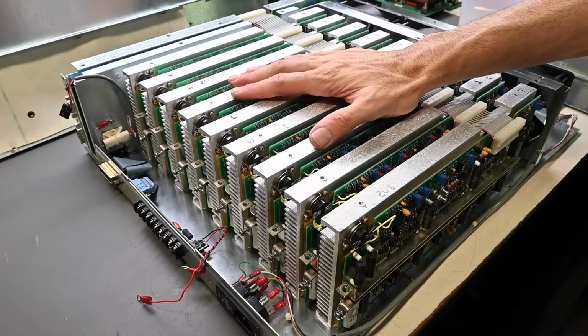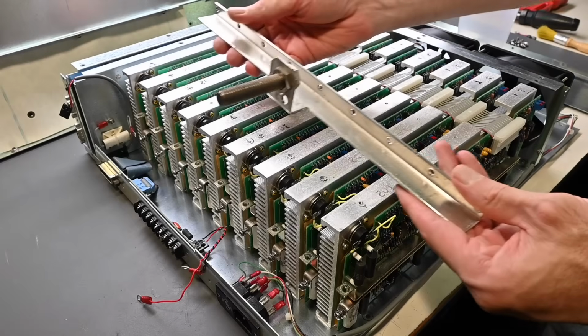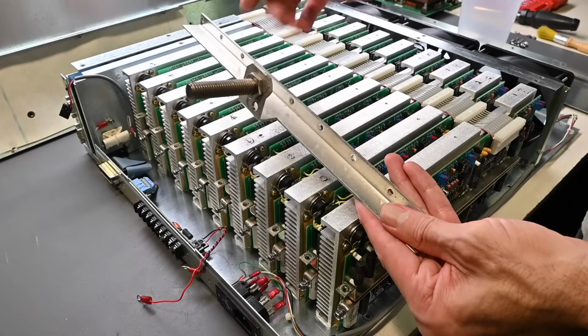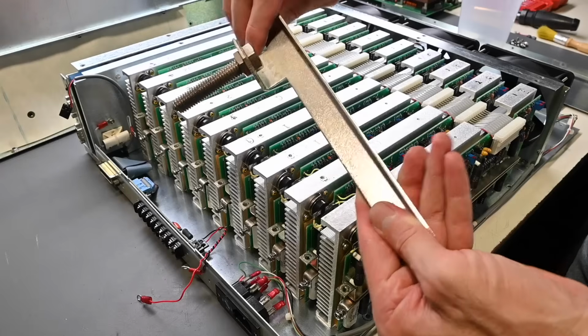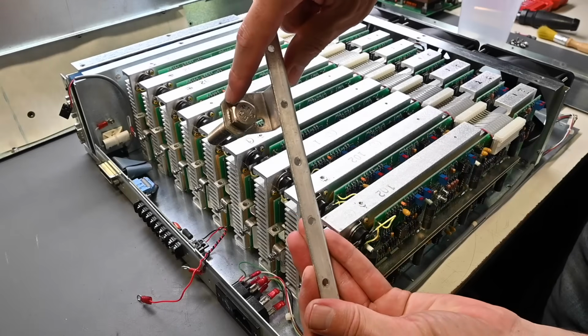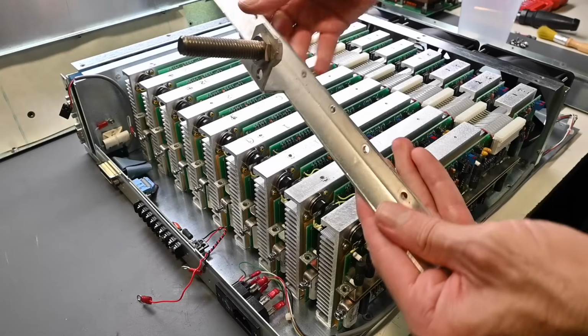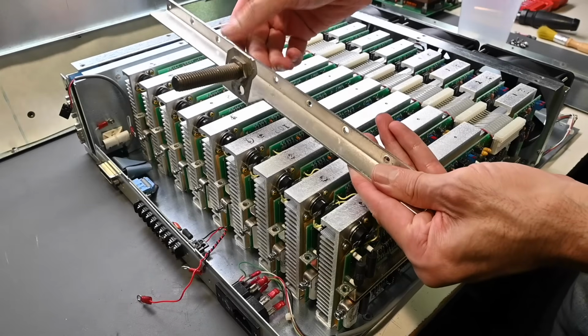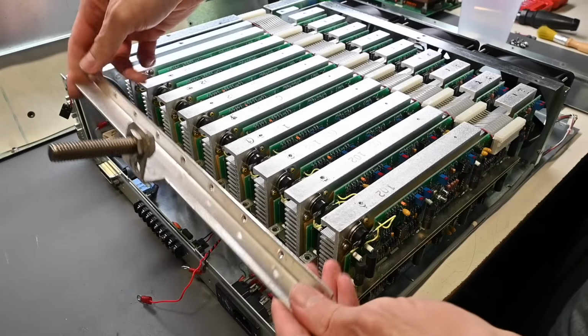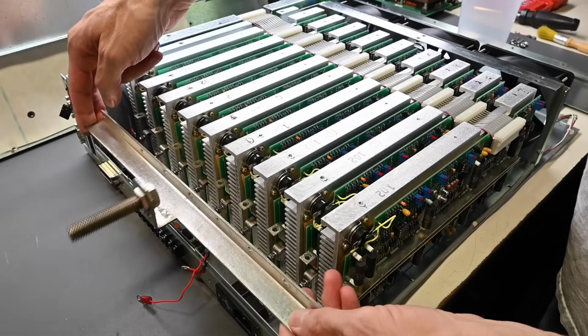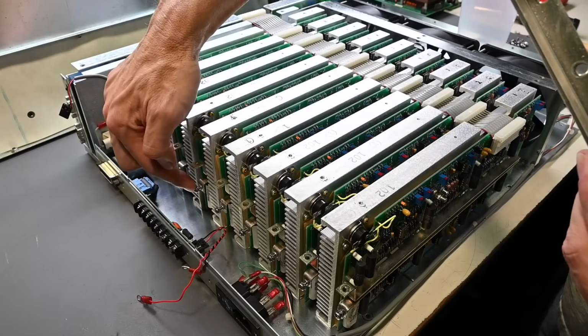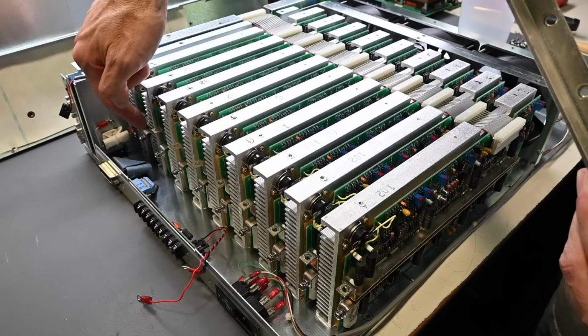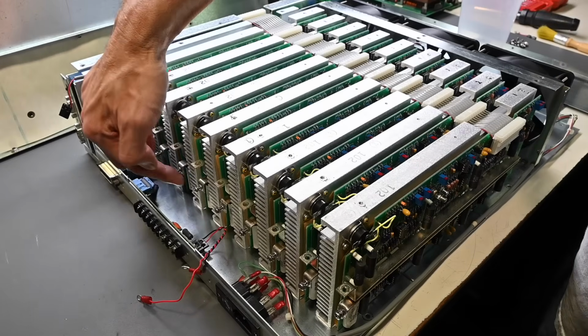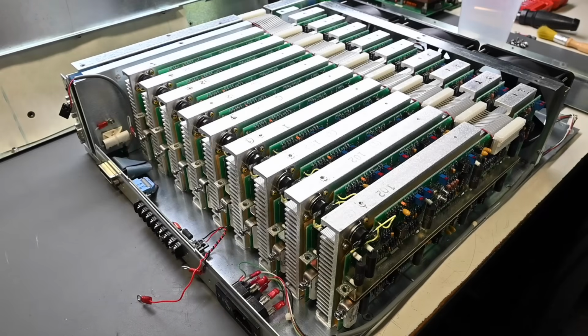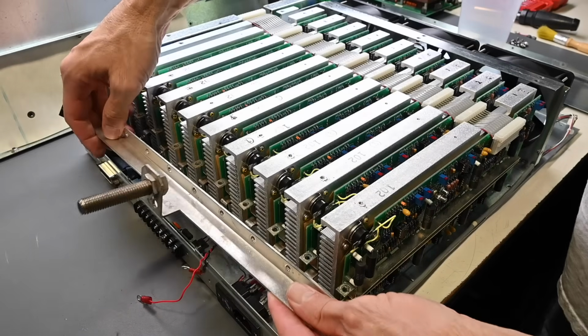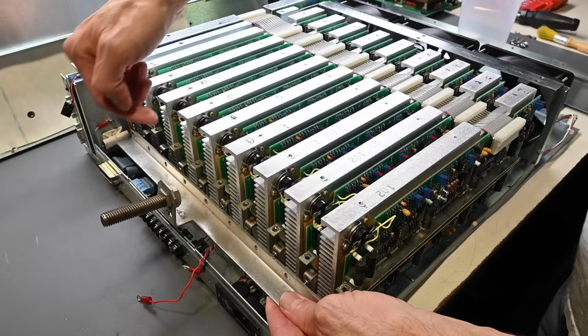All right, all the power modules are in place. So now it's time to install the negative input bus bar. And you can see this large stud is part of the bus bar. The head of this bolt is soldered on, as well as being tightened down with this nut right there. So this bus bar fits in down here, and it's attached by all of these screws to the bus bars that go into the modules. So when I took these screws out, I just returned them back into these places so I didn't lose them. So I'll remove all those screws, get this bus bar down in here, put the screws back in place.